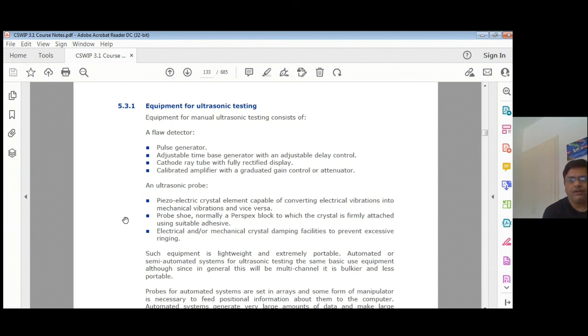Pulse generator, adjustable time base generator with an adjustable delay control, cathode ray tube with fully rectified display, calibrated amplifier with graduated gain control or attenuator. So what are these? Let us understand. Pulse generator, that's what I told you, that it's a probe. That probe in which the electrical current will be sent will generate the pulse, and that pulse generator will be there in the machine. So adjustable time base generator with adjustable delay control. That means a screen where you can adjust the time and the delay control in the equipment. I am showing you the equipment also in the photograph.